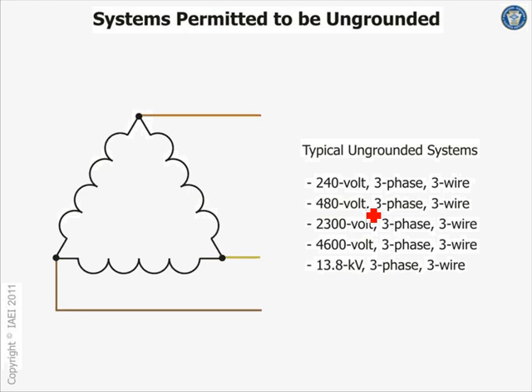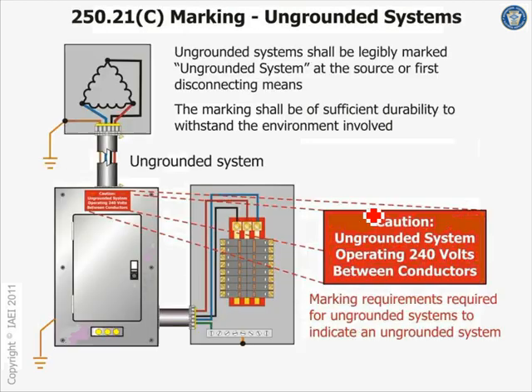So these are the three-wire systems permitted to be ungrounded. Not required, permitted to be ungrounded. But 208/120 is not permitted to be ungrounded if you're to install it in the building. If your system is ungrounded, guys, I know I'm almost running out of time. I just want to mention these are the systems that you do.